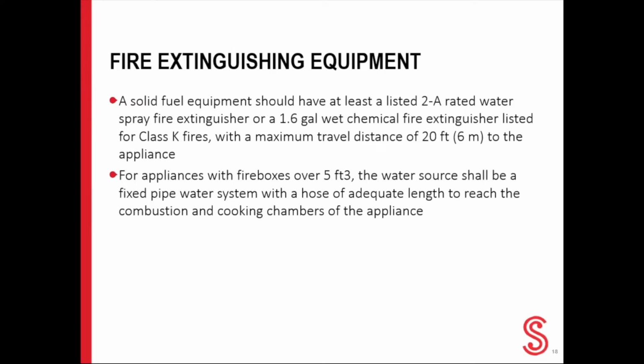In addition to having a fire extinguisher, solid fuel appliances that have fireboxes that are greater than 5 cubic feet should be protected by a water hose with enough length to reach the appliance. That brings me back to my point on the open hearth unit shown earlier. It had to have a water hose installed to be able to reach the fire. The reason why hose protection is important is because unlike gas or electric cooking, there is no way to shut off the fuel source. That is where the water hose comes into play. The hose will provide a continuous water supply to help extinguish the fire.